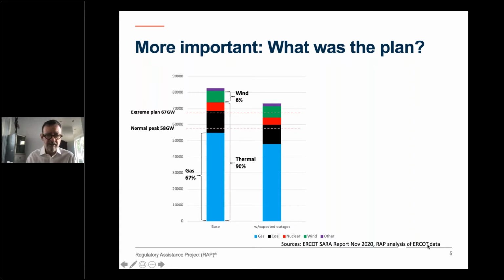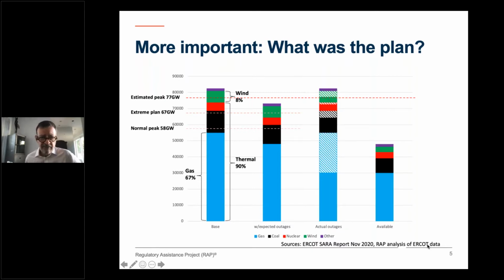What actually happened? The estimated peak was not 67 gigawatts, it was 77 gigawatts. And instead of having about 73 gigawatts of generation available after expected outages, they had less than half of that available, less than 50 gigawatts. Most of the outages, the great majority, were among gas-fired generation.